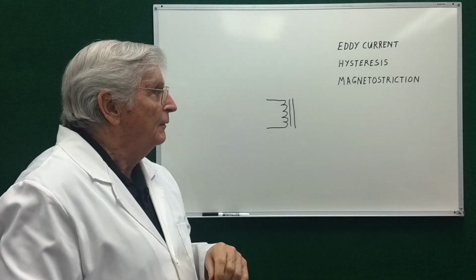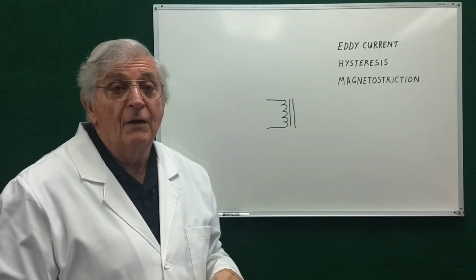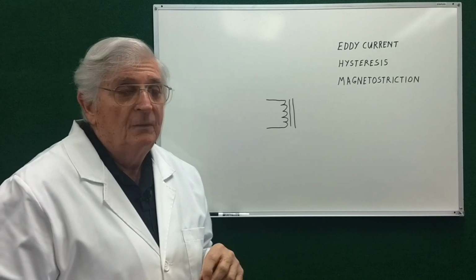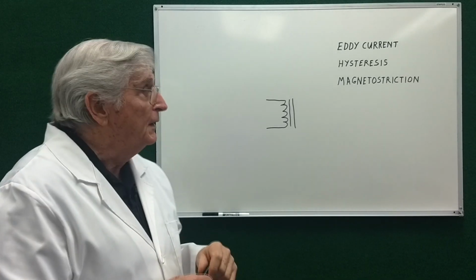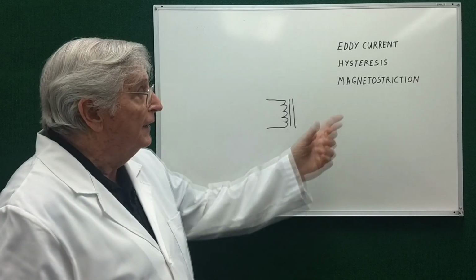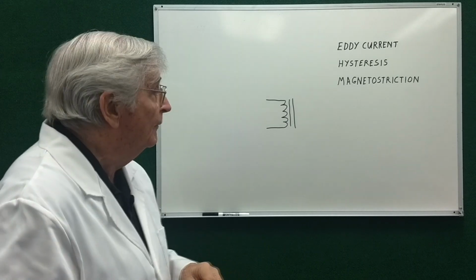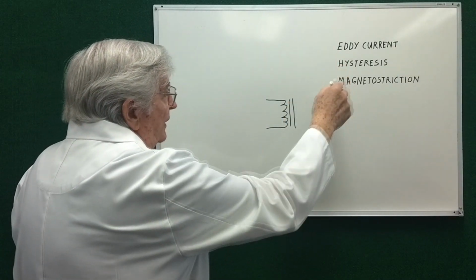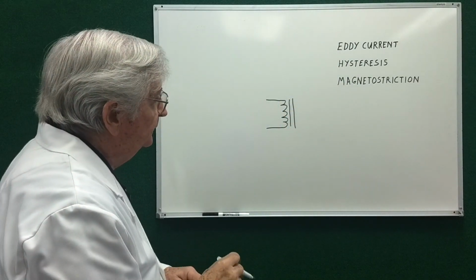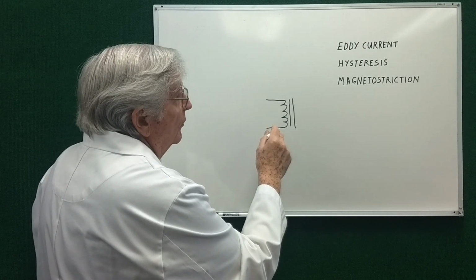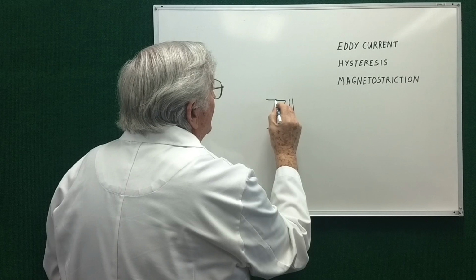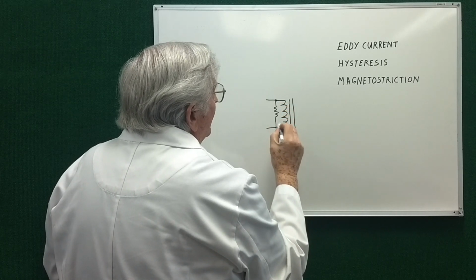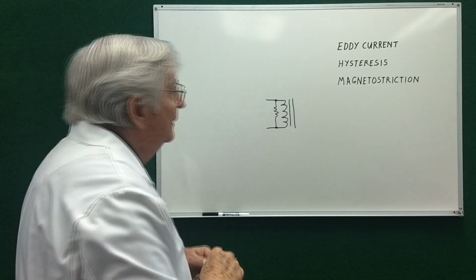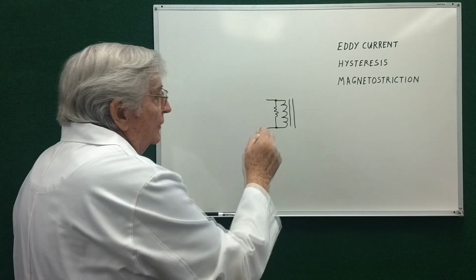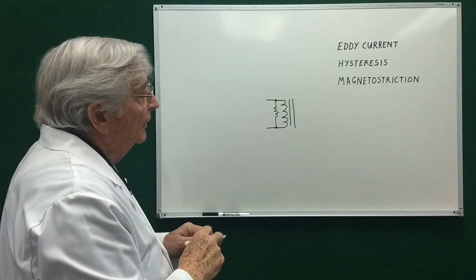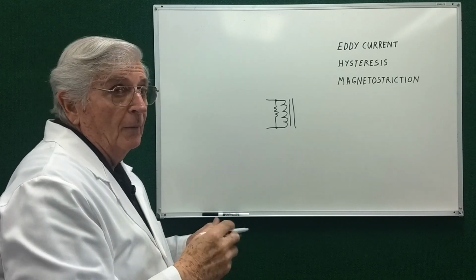In fact, this magnetostriction actually causes the ground to shake near these large transformers because of the huge mass of the core, and the fact that the core is large physically means a lot of magnetostriction will occur. So at any rate, these things determine what we do with the core. For an equivalent circuit of a transformer, these losses are usually represented as a resistor in parallel with the winding. Now this would be a fairly high resistor because these losses are fairly small compared to the IR drop losses in the transformer.